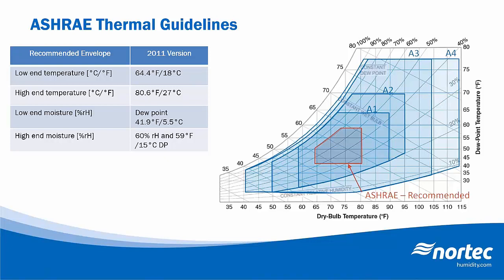So now if we look at the allowable range for an A1 and an A2 class data center, the humidity range is actually 20 to 80%. So these expanded ranges allow data centers in an increased number of locations throughout the world to operate with more hours of economization or free cooling.